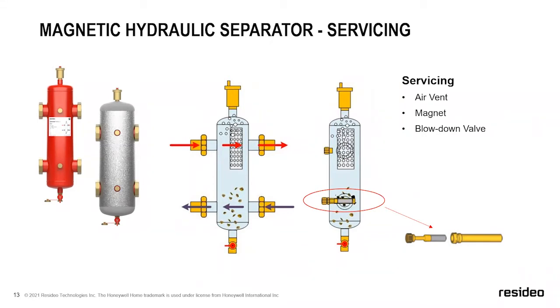So two things take place when that happens. First, the air gets a chance to float up. Instead of being suspended in the water, you get a chance for that air to float because of that velocity change. We do have a little stainless steel grate inside there that does an effective job of helping collect those bubbles, although the bubbles would float inside here without it, but it does help collect them. And then second, because that velocity is dropping as it's passing through, dirt, sediment, etc. is going to fall out of suspension and collect down in the bottom. And then again, that magnet is there to collect any ferrous metals, just to help make sure none of that stuff moves through.